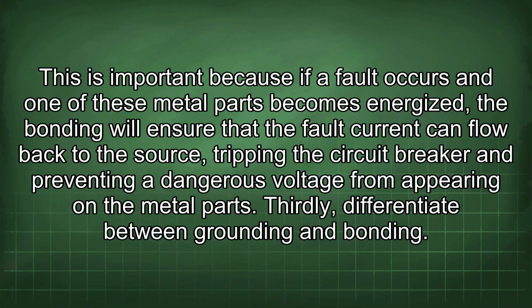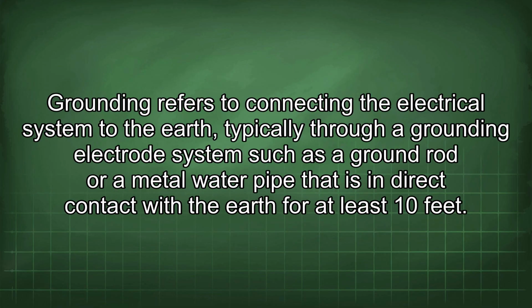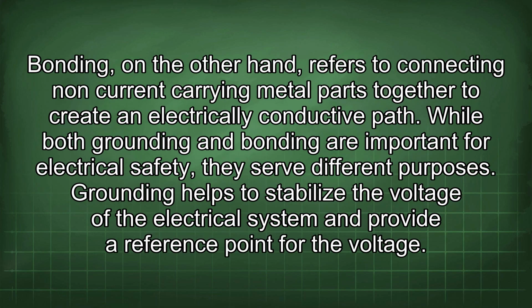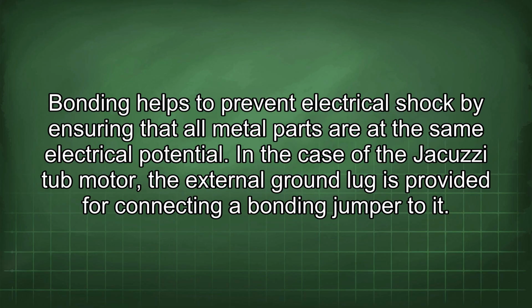Thirdly, differentiate between grounding and bonding. Grounding refers to connecting the electrical system to the earth, typically through a grounding electrode system such as a ground rod or a metal water pipe that is in direct contact with the earth for at least 10 feet. Bonding, on the other hand, refers to connecting non-current carrying metal parts together to create an electrically conductive path. While both grounding and bonding are important for electrical safety, they serve different purposes. Grounding helps to stabilize the voltage of the electrical system and provide a reference point for the voltage. Bonding helps to prevent electrical shock by ensuring that all metal parts are at the same electrical potential.